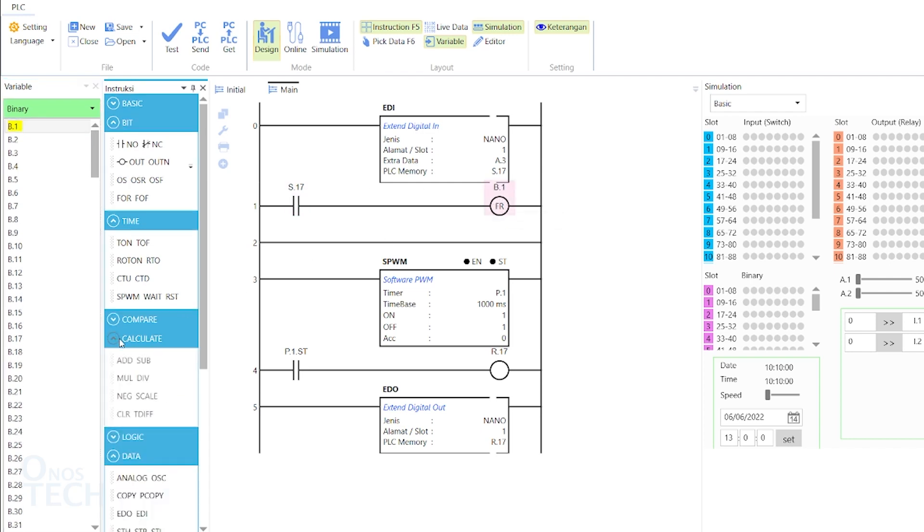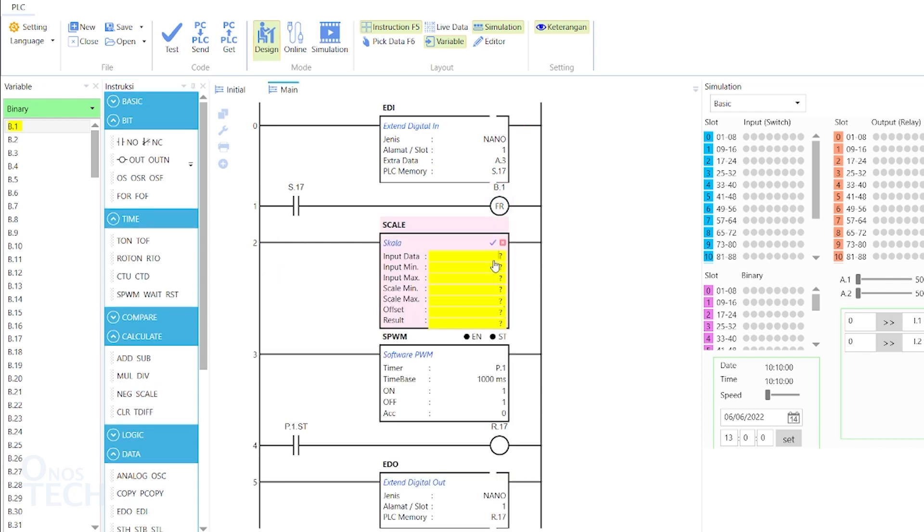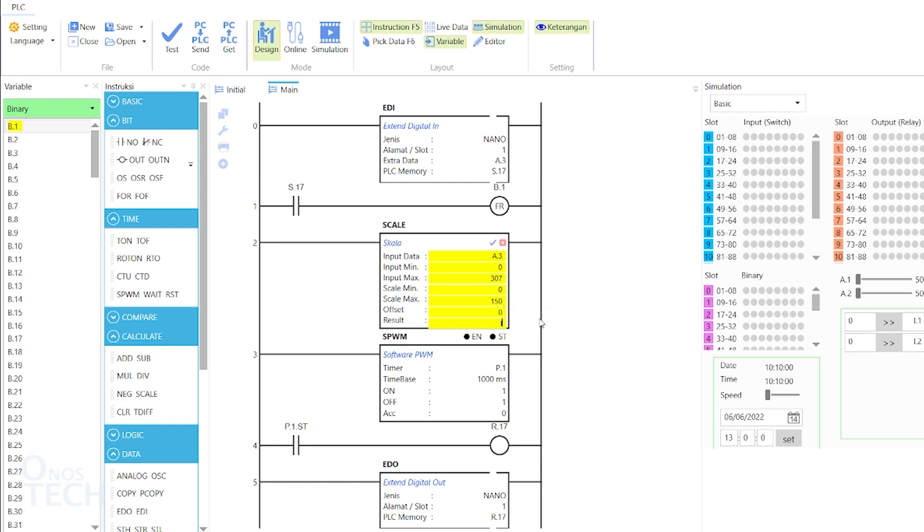Drag a scale instruction to the third rung. Set the input data to A.3, the input min to 0, the input max to 307, the scale min to 0, the scale max to 150, offset to 0, and the result to I.1.